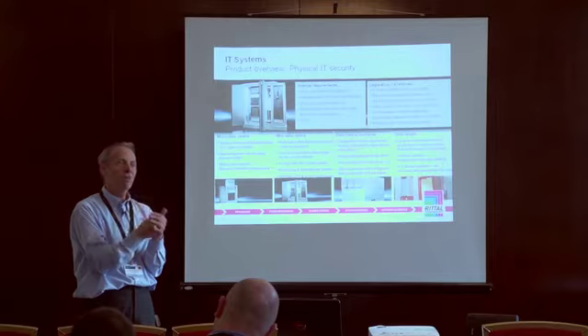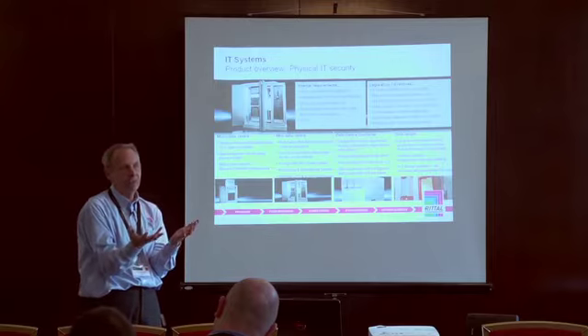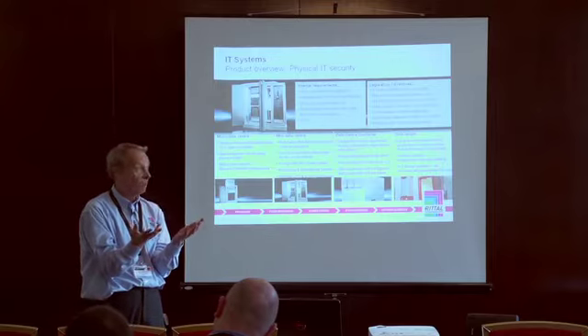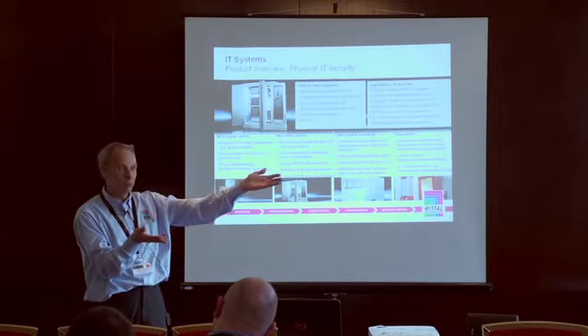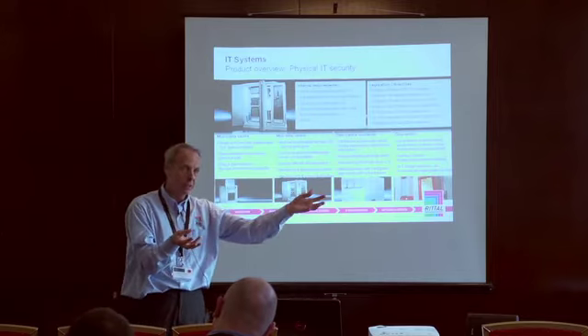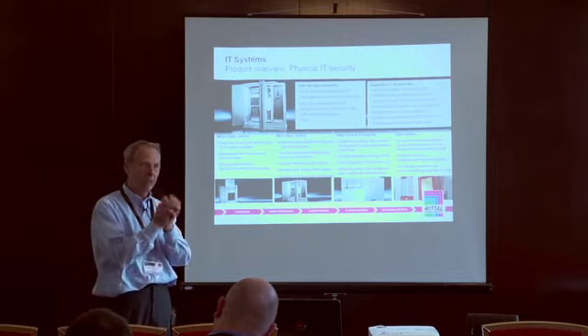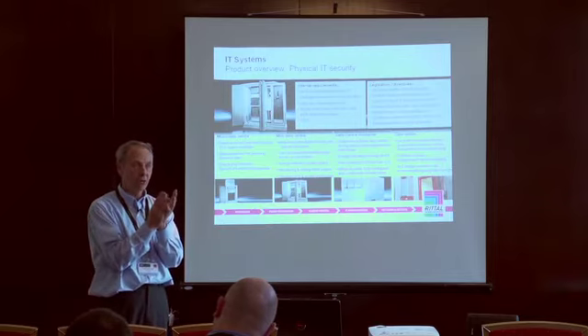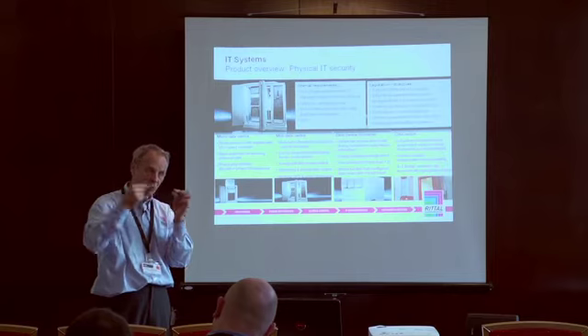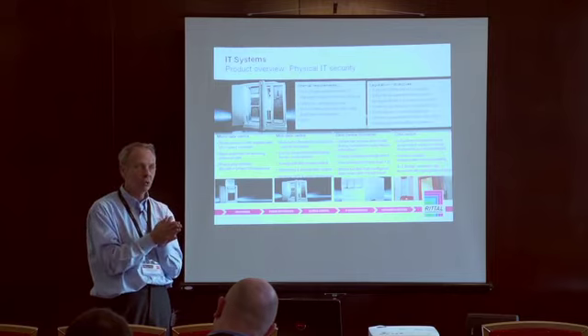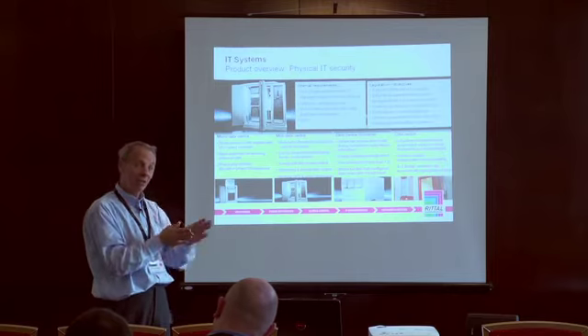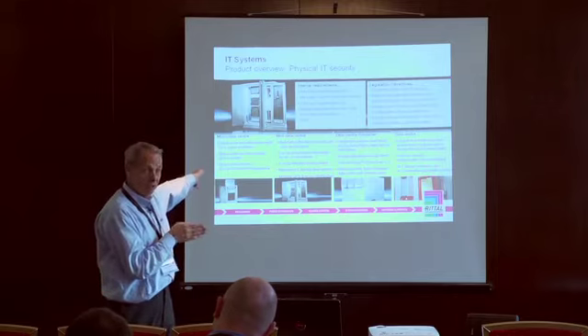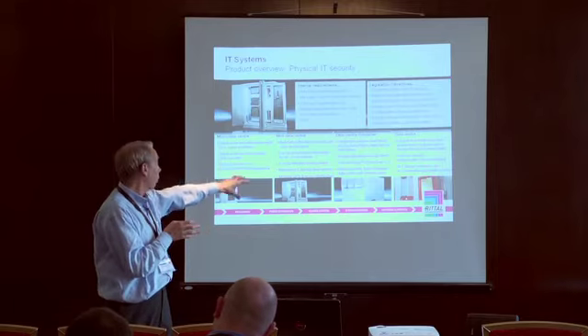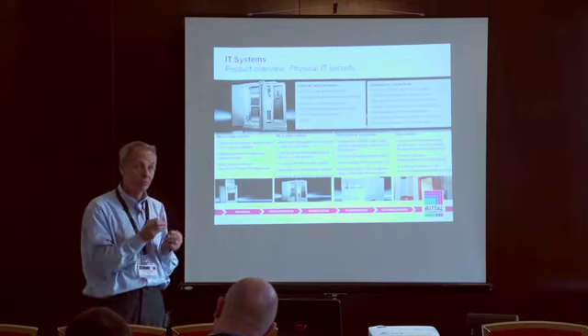So if you had a major fire, say 450 to 500 degrees C - standard car petrol fuel ignites at around 400 degrees C - this absorbs the heat, expands, and chokes off the cables so nothing can pass through the cables or pipes. That's what they use on oil rigs, and we use that same technology on our safes, our containers, and our modular rooms, which we'll go through.